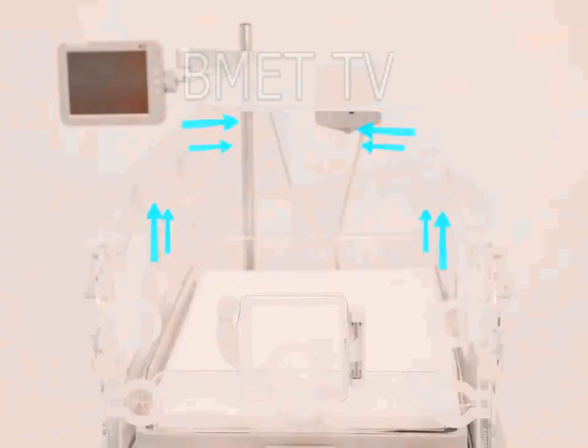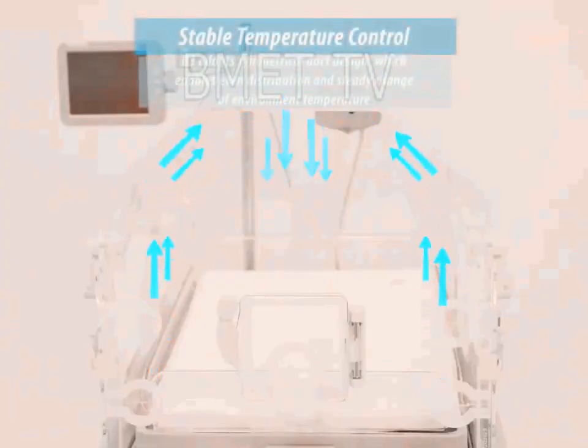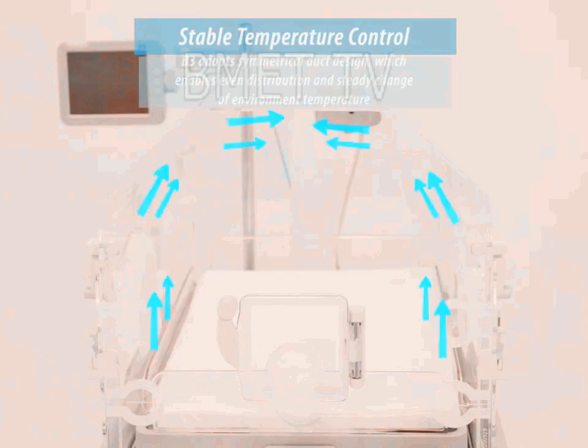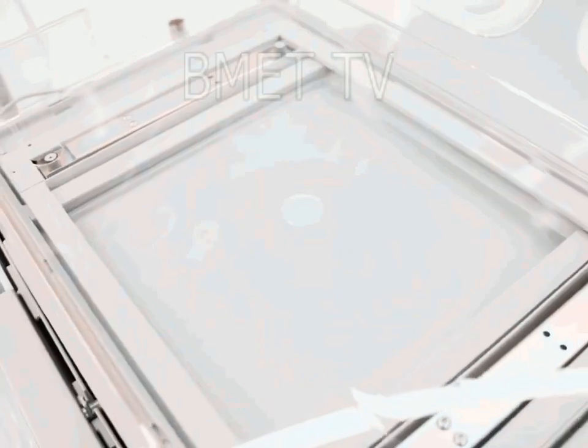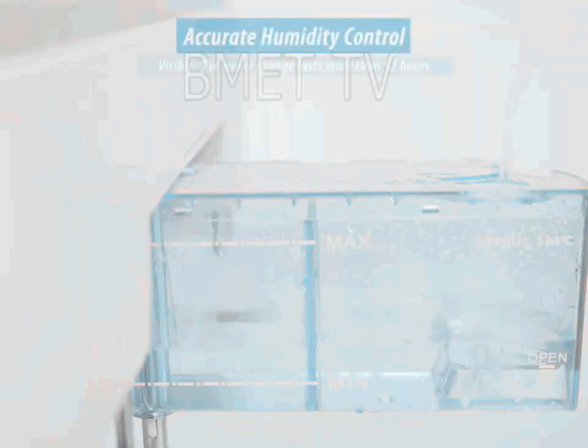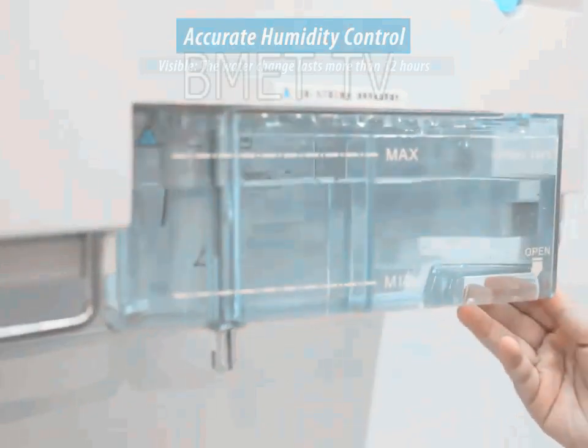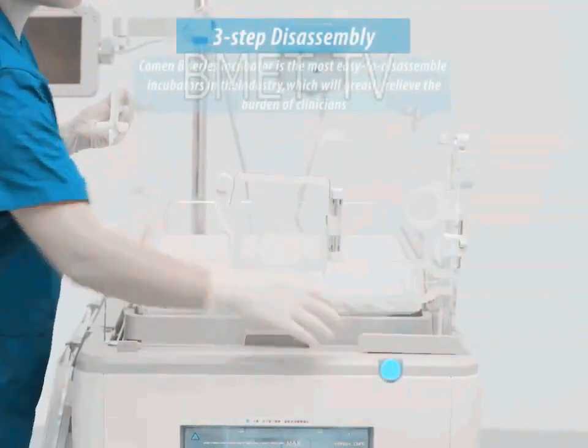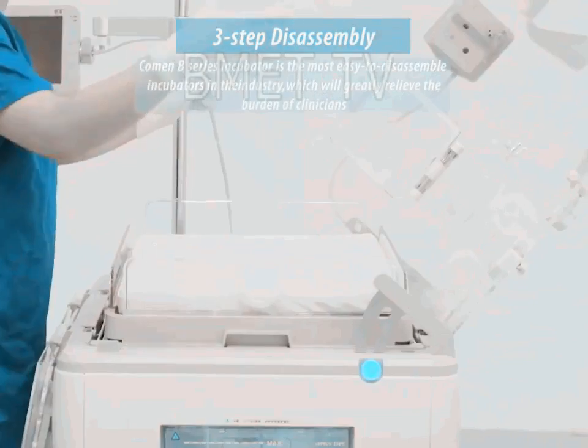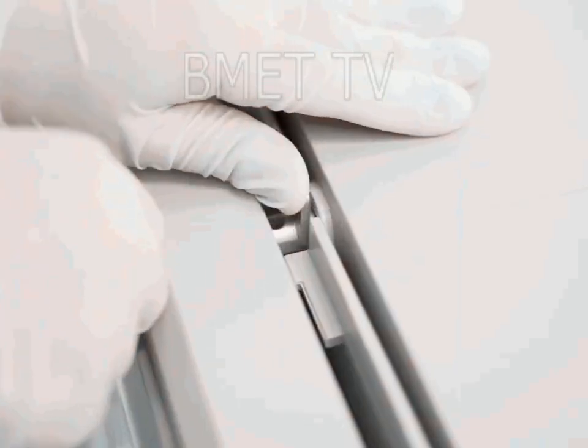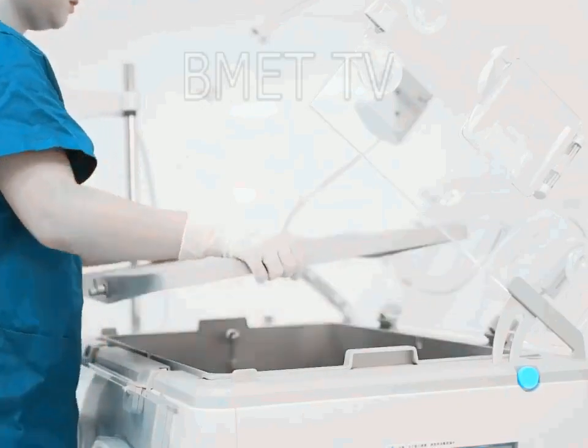Fully enclosed, an infant incubator carefully controls its environment to protect infants during their earliest stages of life when they're most vulnerable. The incubator may include an AC-powered heater, a water container to add humidity, a motorized fan to circulate the warm and humid air throughout the cabin of the incubator, a control valve through which oxygen may be added, and a servo control to help regulate air temperature, with a temperature-sensing thermistor taped to the infant's abdomen. Hand access ports with doors limit the introduction of cooler air while the infant is being handled, and the hood or side panel can be opened to gain greater access to the infant.